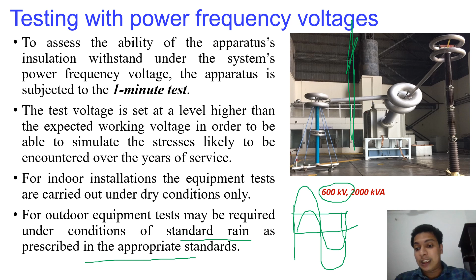Not all equipment is installed indoors. We may have a transformer installed indoor, and an outdoor insulator also. For an indoor system, testing is done indoor only, since atmospheric conditions won't affect it much. But for an overhead insulator, atmospheric conditions definitely affect it, so we use standard rain as prescribed by appropriate standards. This is also considered in power frequency testing.